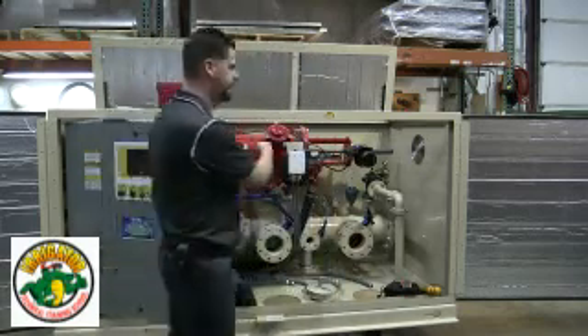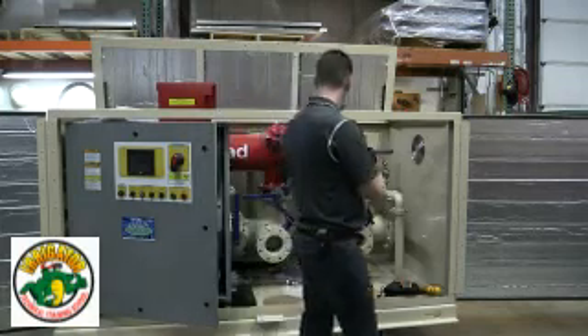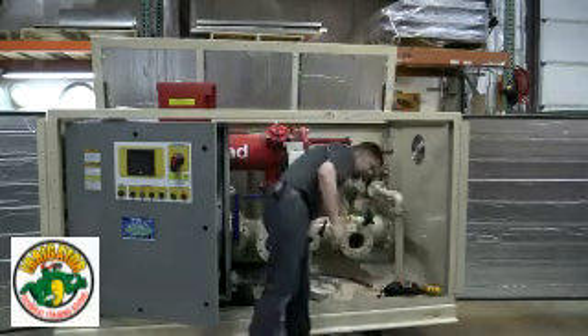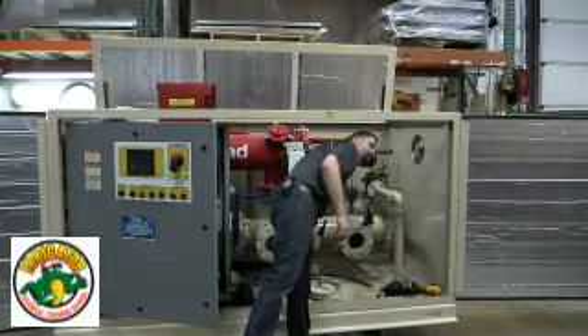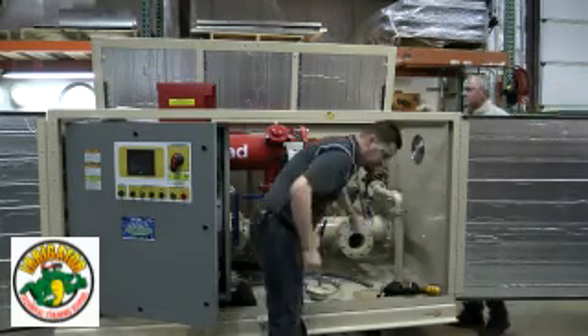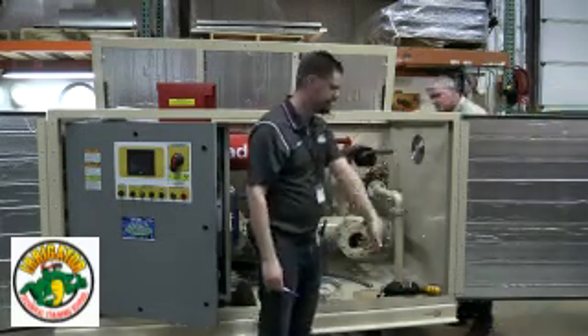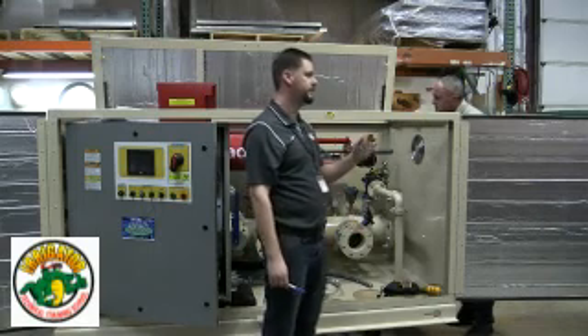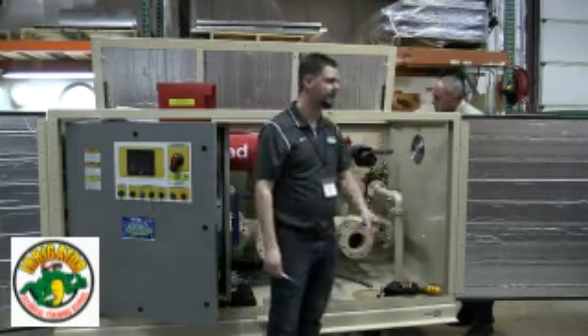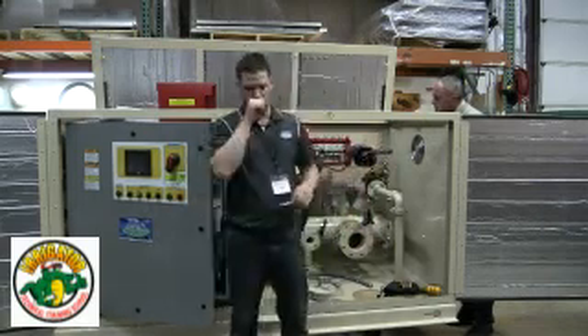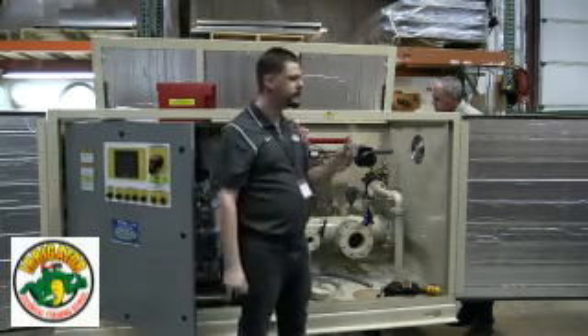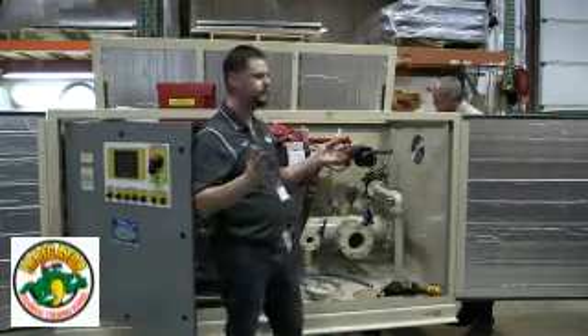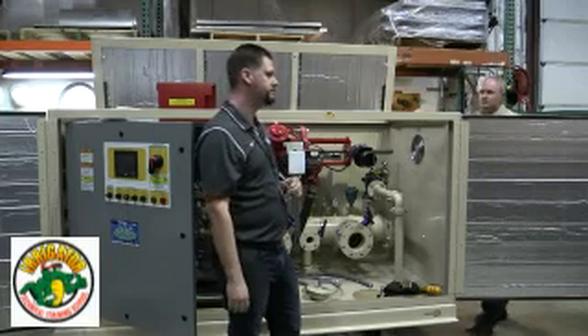But those are adjusted by turning this whole plastic cover. Oh, yeah. If you're on the top looking down, counterclockwise is a lower pressure at which the switch will actuate. Clockwise is a higher pressure. Now the pressure switch we want about 15 pounds above our set point.